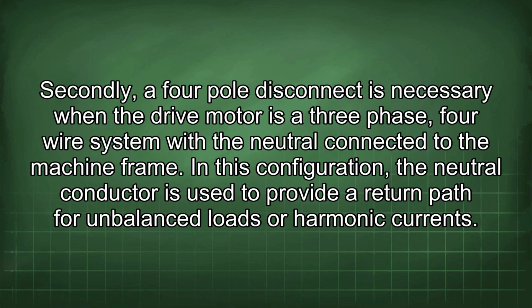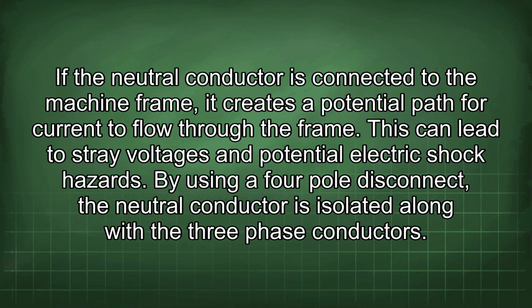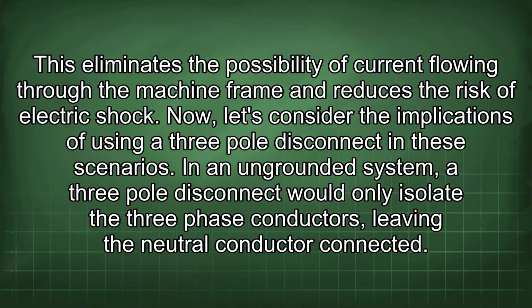Secondly, a 4-pole disconnect is necessary when the drive motor is a 3-phase, 4-wire system with the neutral connected to the machine frame. In this configuration, the neutral conductor is used to provide a return path for unbalanced loads or harmonic currents. If the neutral conductor is connected to the machine frame, it creates a potential path for current to flow through the frame. This can lead to stray voltages and potential electric shock hazards. By using a 4-pole disconnect, the neutral conductor is isolated along with the 3-phase conductors. This eliminates the possibility of current flowing through the machine frame and reduces the risk of electric shock.